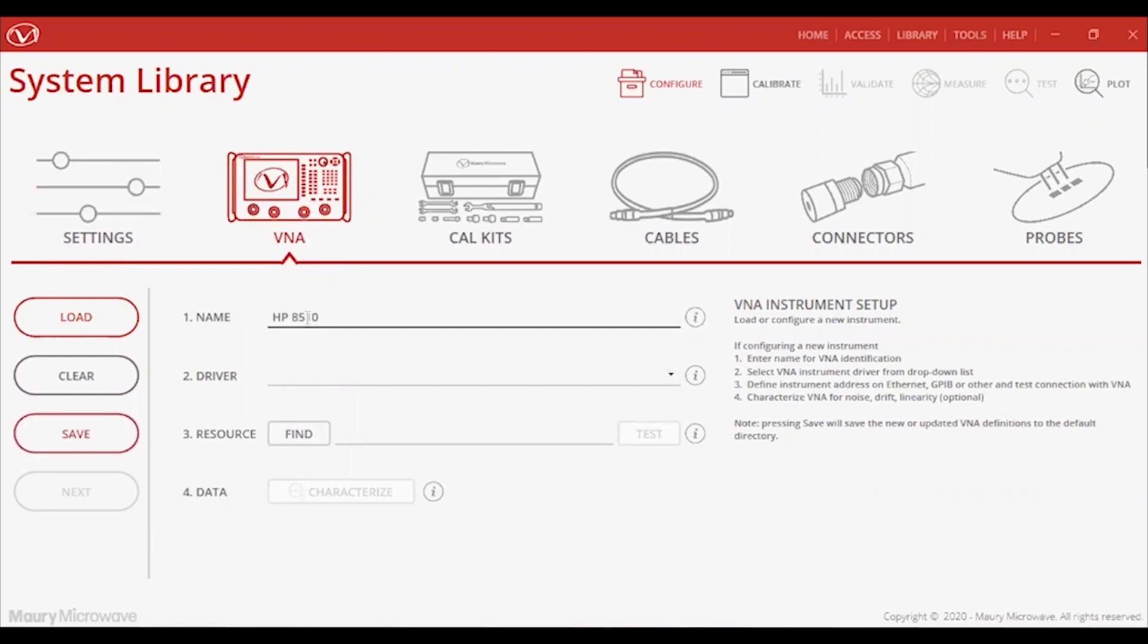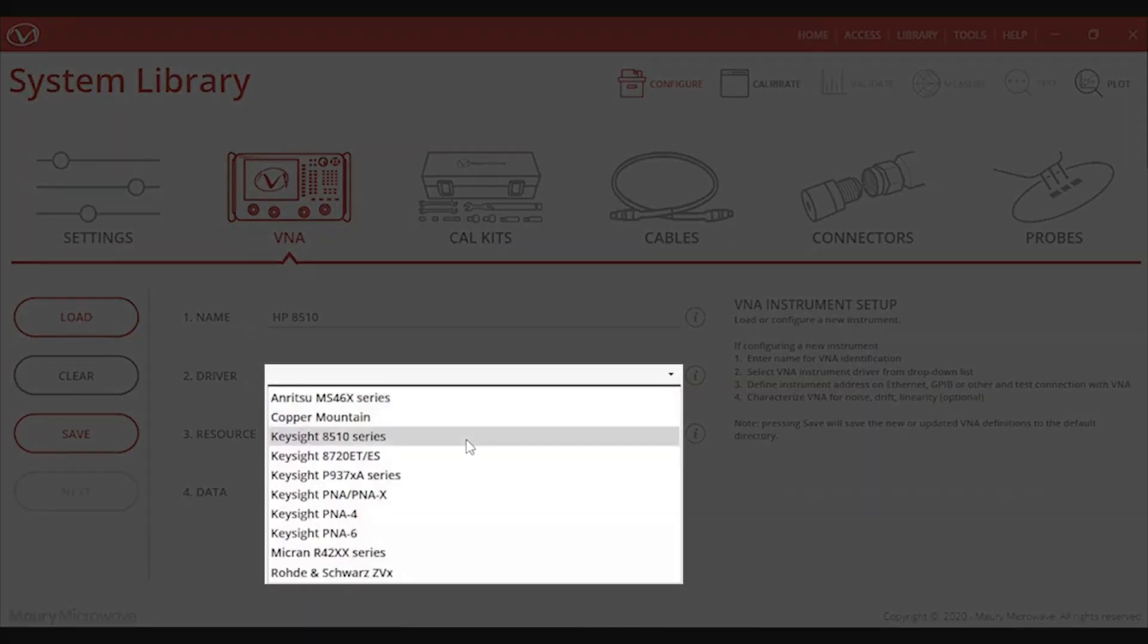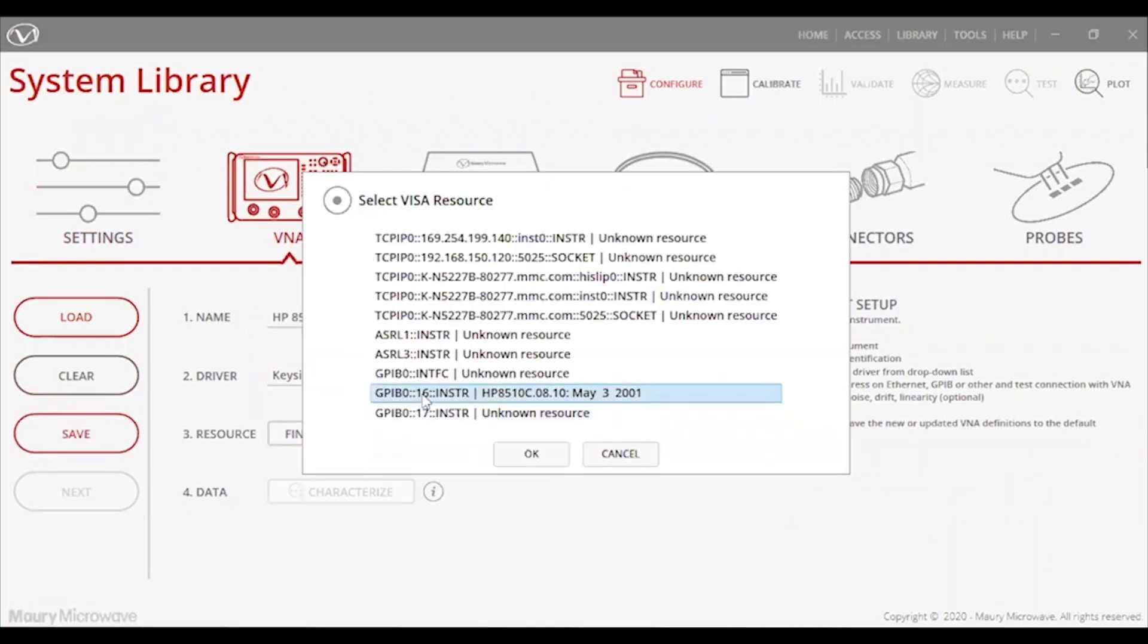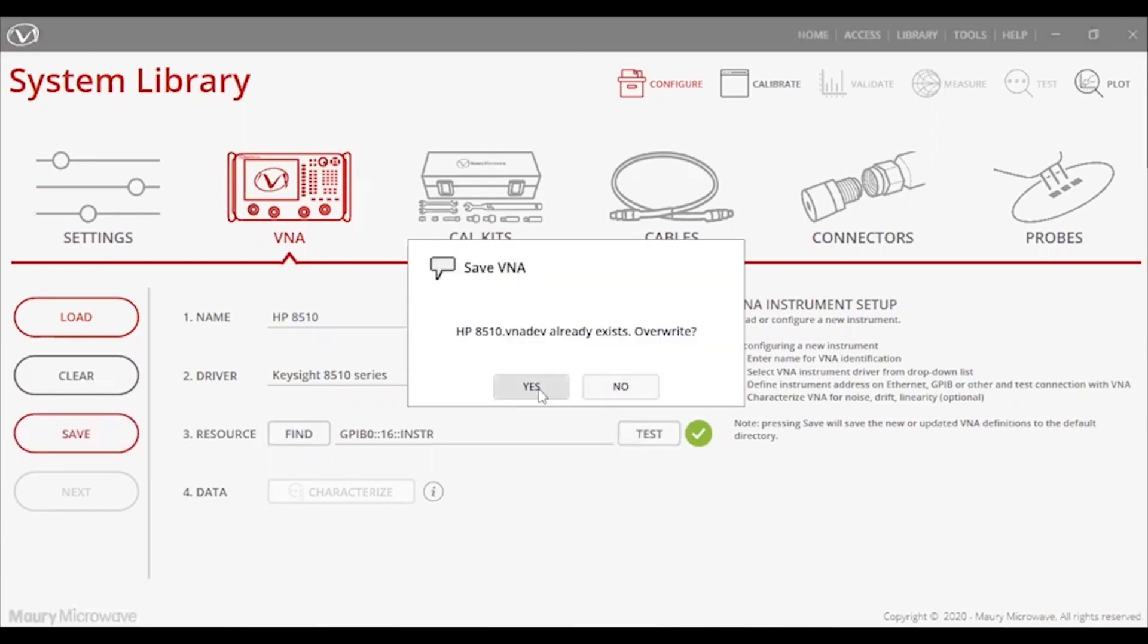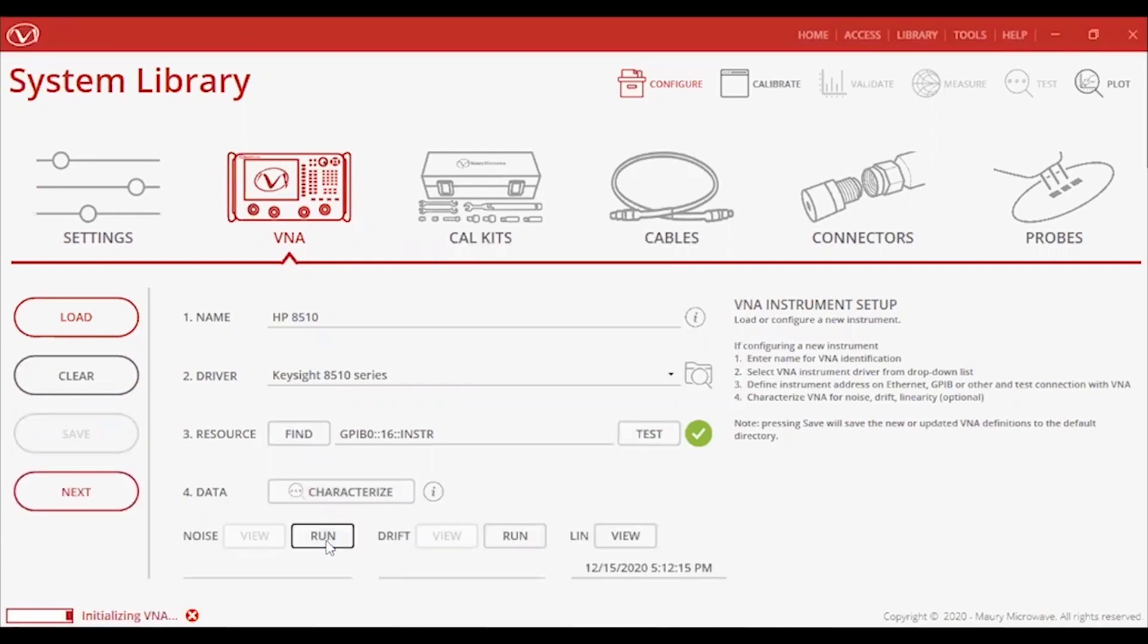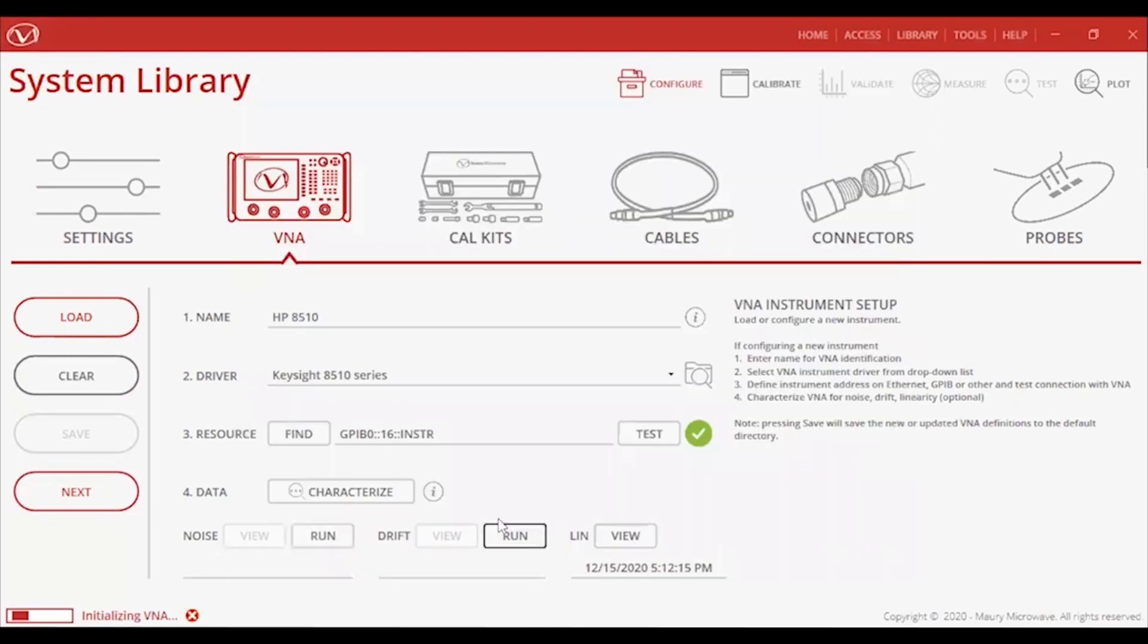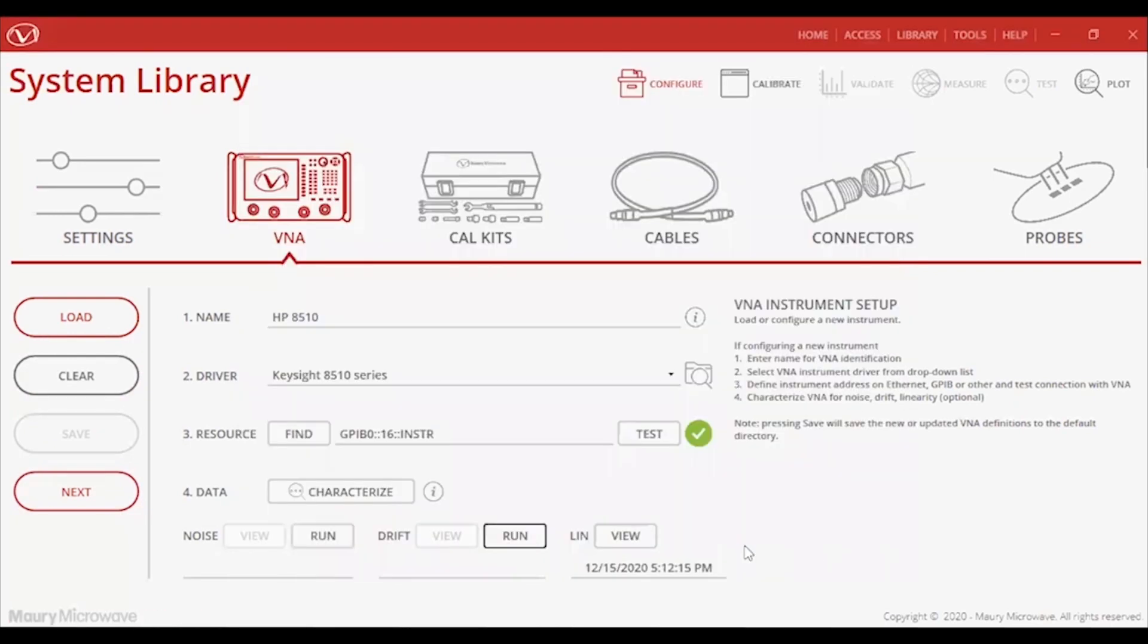I'll go ahead and start things off by selecting the Keysight 8510 VNA model from our extensive list. You will notice that we have support for most commercial VNAs, including other discontinued and obsoleted models, which may also suffer from similar problems like my 8510. As an added benefit, not only will InSight take over the front end from the VNA, but I can also use it to characterize noise and drift, adding the VNA's uncertainties to the total budget.